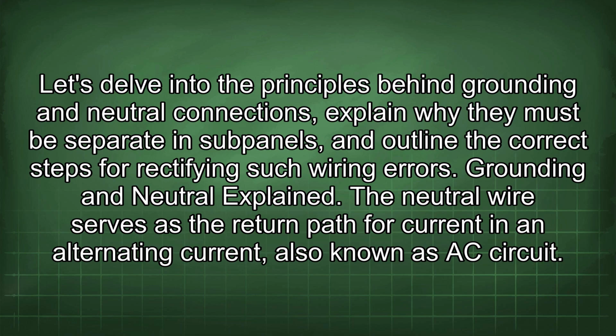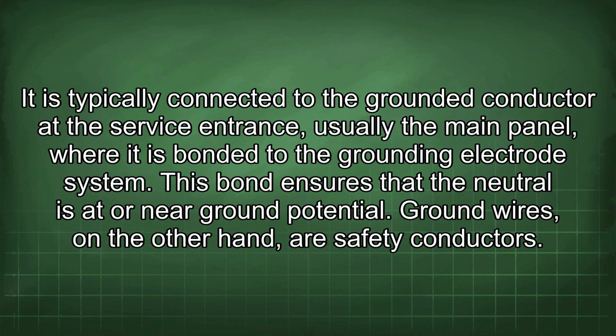Grounding and neutral explained. The neutral wire serves as the return path for current in an alternating current, also known as AC, circuit. It is typically connected to the grounded conductor at the service entrance, usually the main panel, where it is bonded to the grounding electrode system. This bond ensures that the neutral is at or near ground potential.